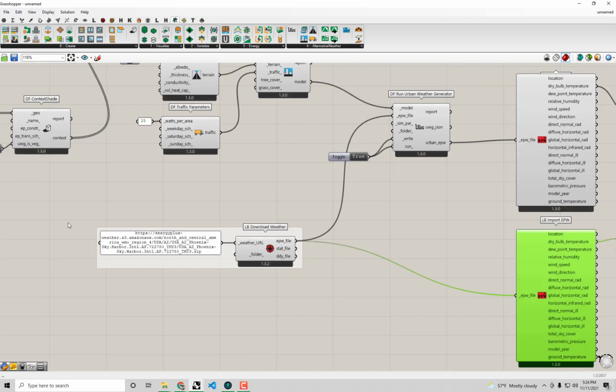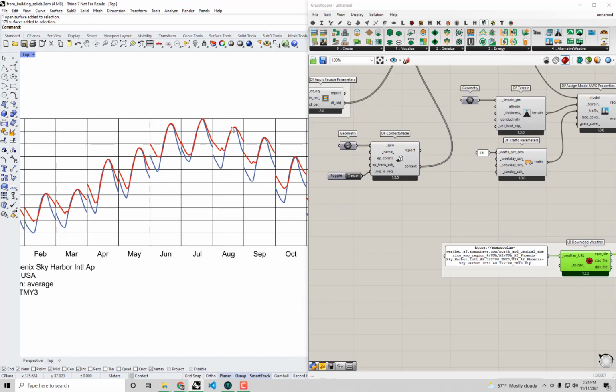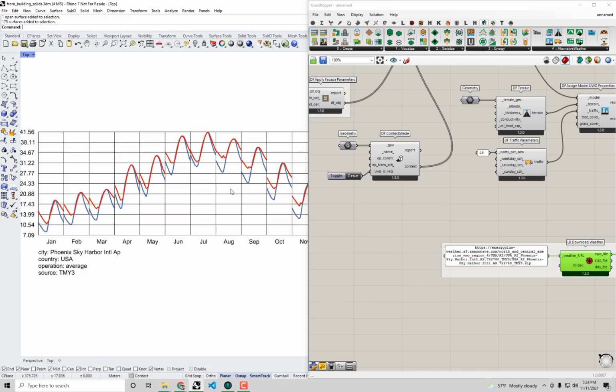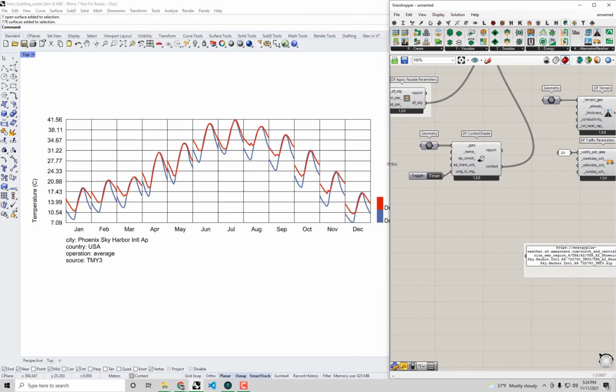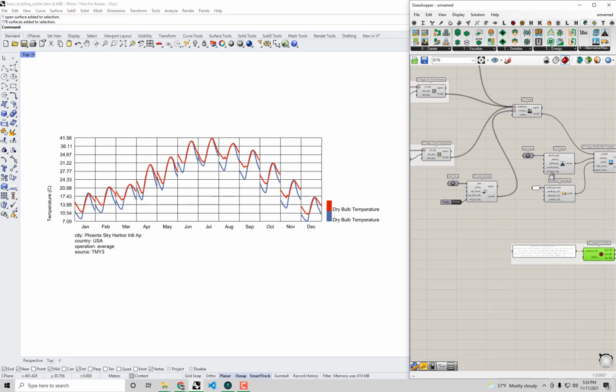Now, I'll give a disclaimer. I know I picked this climate of Phoenix particularly because I know it can have a really intense urban heat island effect, right? Particularly these dry climates that have big diurnal swings, big differences between nighttime and daytime temperatures. That is probably where you're going to find some of the largest urban heat island effects. I mean, obviously, the highest density areas will also have big effects, but more often than not, you'd find in a climate, especially a heating dominated climate like Boston or Buffalo, which we looked at in the series, you're going to find a much smaller impact from urban heat island on the energy use and on thermal comfort overall. In fact, because those climates are heating dominated, the urban heat island effect usually helps mitigate. It can even reduce the EUI a little bit. But in this case, in Phoenix, I'm sure we definitely see an increase in energy use because of the urban heat island effect. So again, use your judgment.